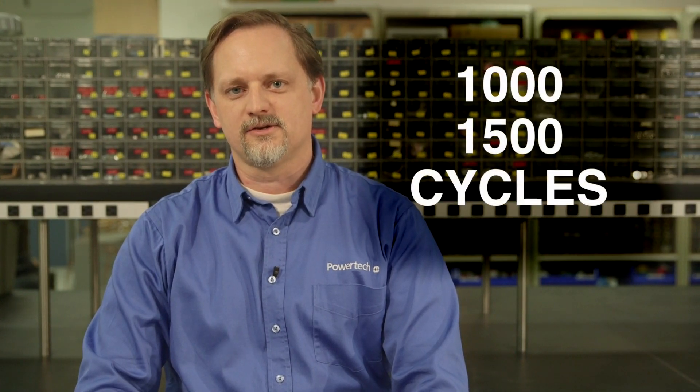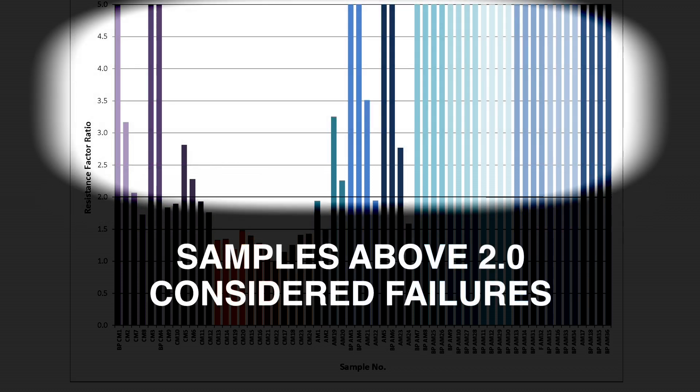Resistance and temperature values were recorded throughout the test and were evaluated at a thousand and 1500 cycles. This chart shows an evaluation of the resistance after a thousand cycles using the method from the IEC standard. Each vertical bar represents one test sample. The height of each bar is the ratio of resistance at a thousand cycles compared to the resistance at the start of the test. The line at the ratio of two indicates the maximum allowable ratio according to the IEC standard. A resistance ratio above this line is considered a failure according to IEC.